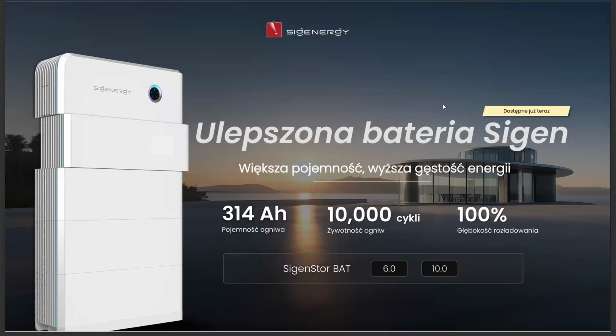3. 100% DoD, capacity the user can actually use. A common question concerns depth of discharge, DoD. In our case, the user gets 100% usable capacity. At first glance, this may raise concerns. Is it safe to discharge the battery to zero?